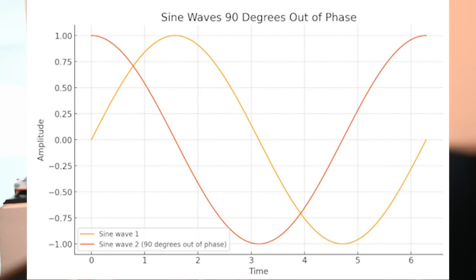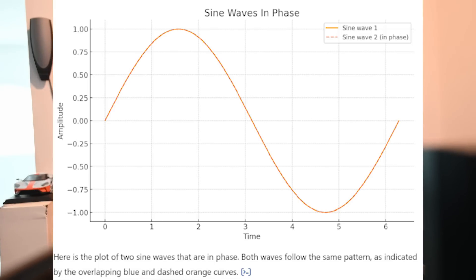These three things must be true: Number one, the voltage output of both generators must be the same and must match the voltage of the bus. Number two, the phase angles have to be exactly the same — when looking at the sine wave outputs, they have to line up perfectly, within an oscilloscope. Number three, once aligned and the switch is thrown, both generators must share an equivalent output load so one generator doesn't try to become the load of the other — both supplying power, not drawing it.